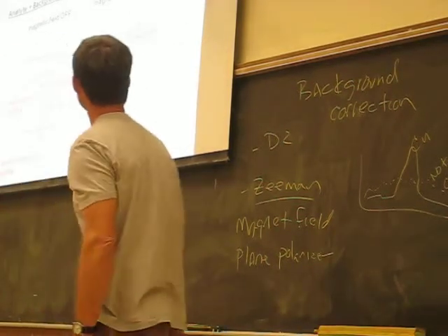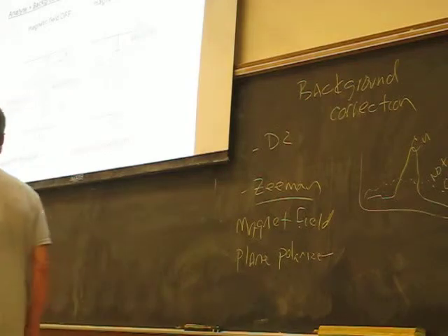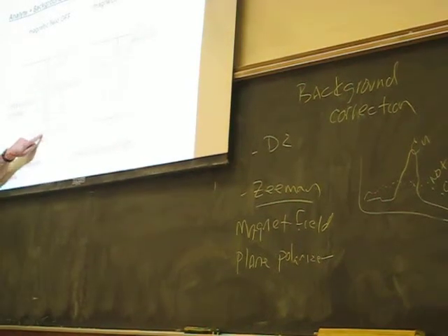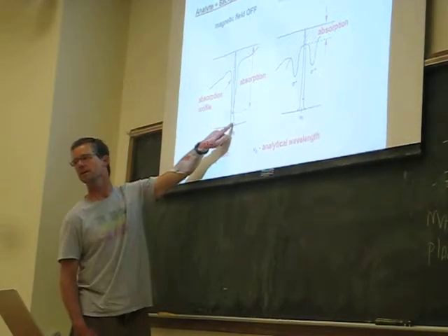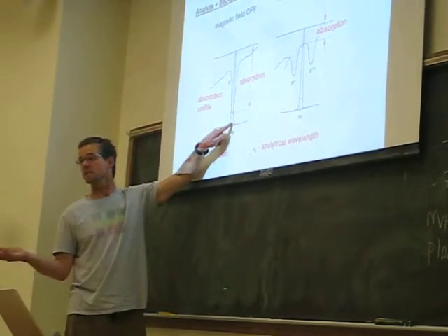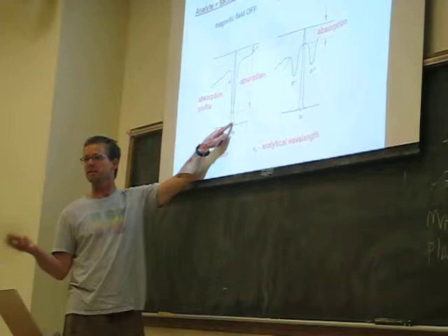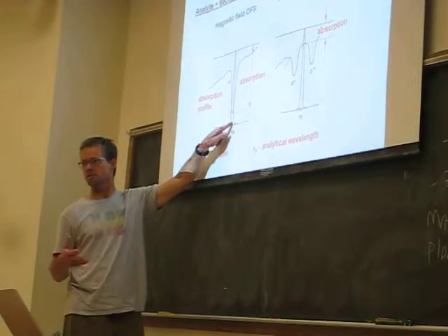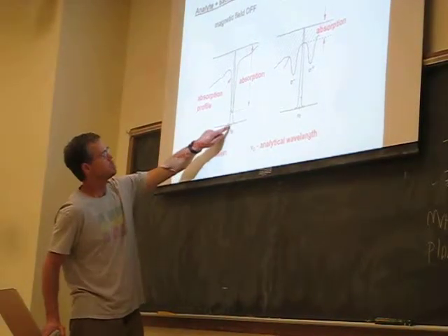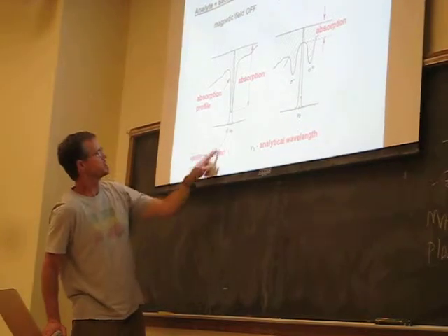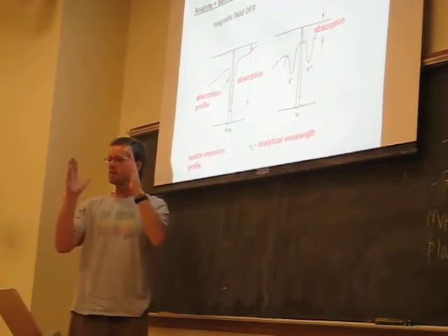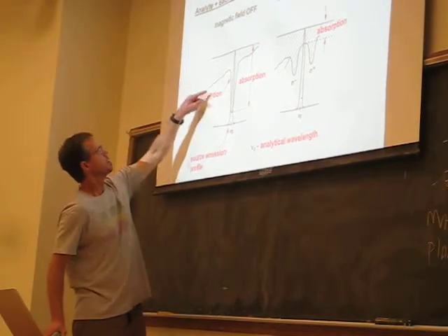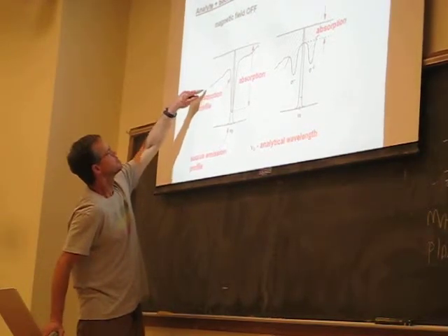And this is a better way to illustrate that. So this is the light that would be coming from your hollow cathode lamp. So this is your emission profile, shown right here. And so in your case, say if we were measuring copper on a graphite furnace atomic absorption spectrometer with a Zeeman background correction, we would be generating this one emission atomic line for copper here. And then during our read cycle for the instrument, we would be generating an absorption profile.